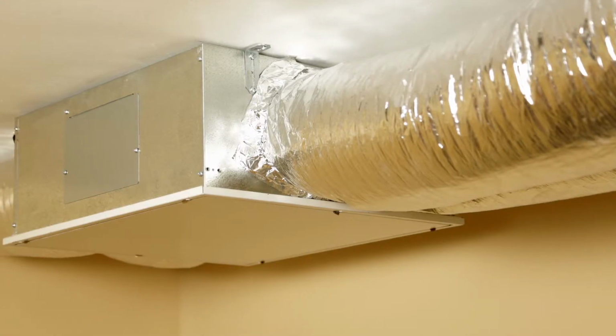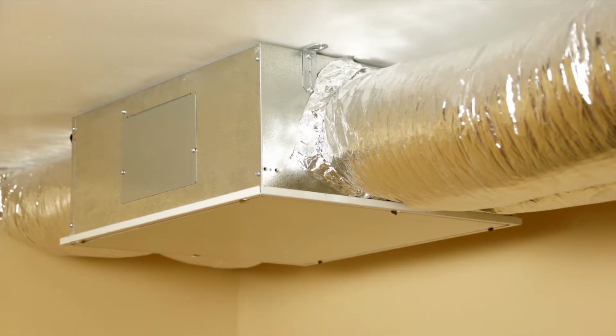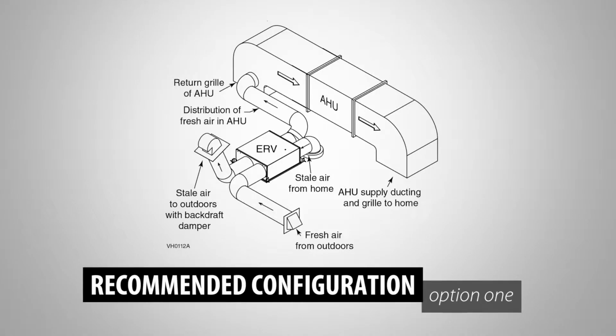There are two ways to integrate the ERVS100 with the air handling unit. The recommended configuration distributes fresh air from the ERVS100 into the air return of the AHU. In this configuration, the connection should be made as close as possible to one of the AHU return grills to ensure proper functioning of the built-in fresh air damper. In this configuration, you likely will want to install the stale air exhaust registers in a bathroom, kitchen, or living room. If installing a stale air exhaust register in a bathroom, this eliminates the need to add a common bath exhaust fan in the bathroom.